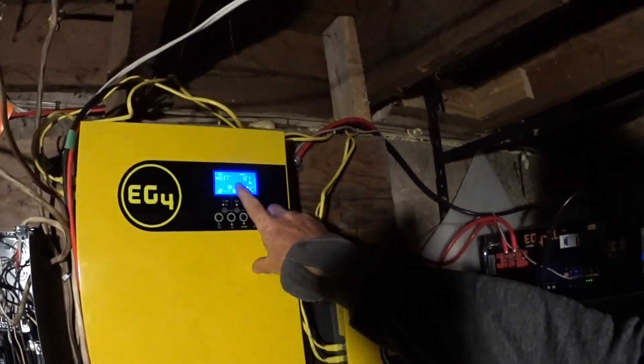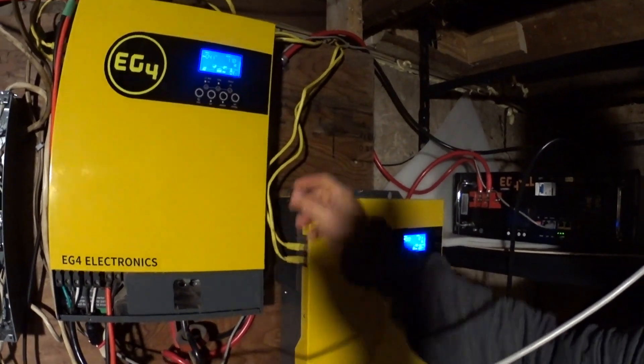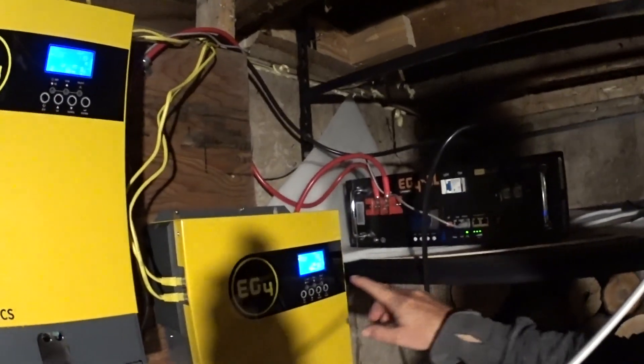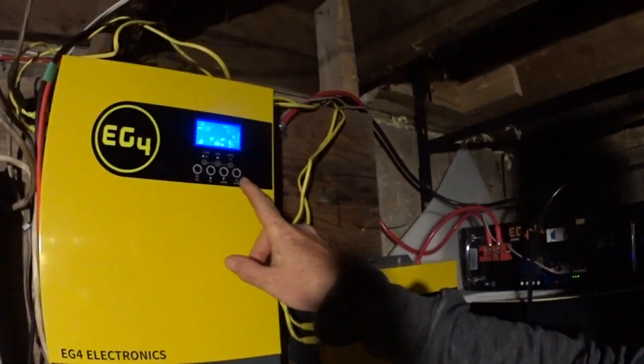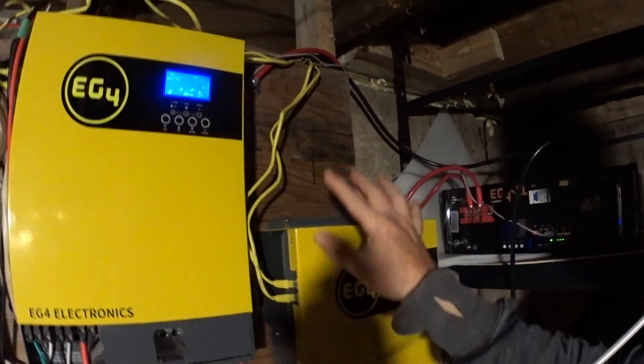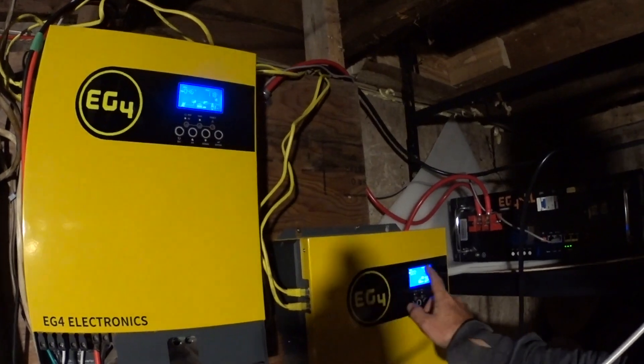I had a flashing 19 here. These units are in split phase 120/240 configuration with the communication cables — one single cable to communicate with the battery and the BMS. With them both set to LI4 for battery type, they would flash 19. Even after I got everything working, 240 volts working, everything's great, but they wouldn't stop.